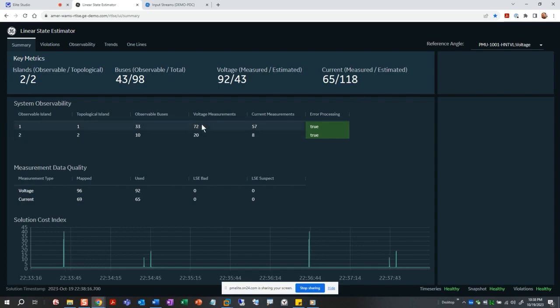As our island splits into two islands, we're going to keep track of the observable buses in each island and the voltage and current measurements, make sure that our error processing is good, and then our data quality across the system. So also the solution cost index, so that's just a measurement of the effort that the linear state estimator is going through in order to get a solution. The linear state estimator is running at the sub-second rate, pretty much at the same rate that the incoming data is coming at. So it's very fast and robust.